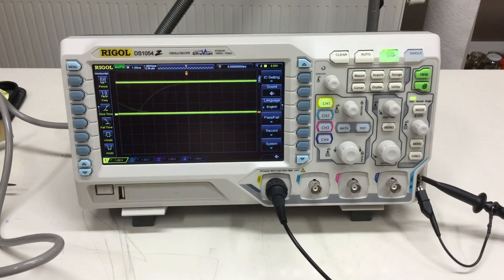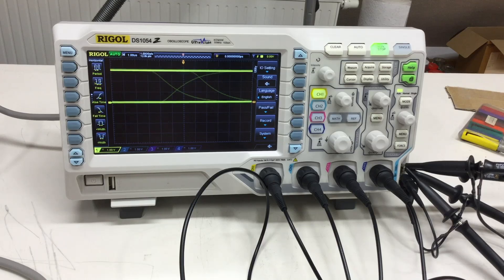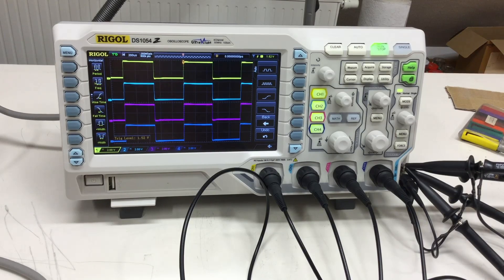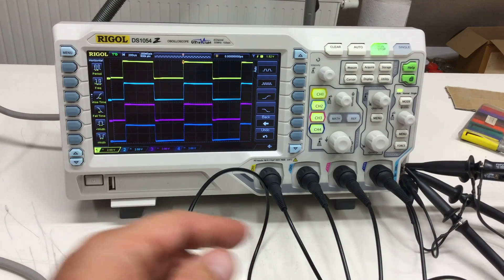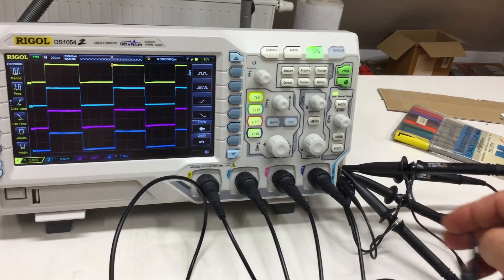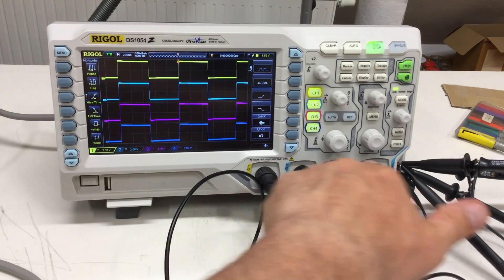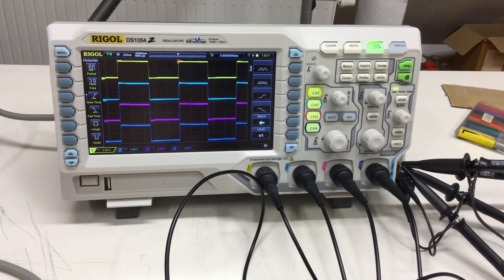We see something! Next probe connected. Let's see what happens if I press Auto now. All four channels come on — wonderful! I have a few ground lines dangling here, but all the BNC cable shields share the same ground, so the signal is coming through. Nice and colorful.